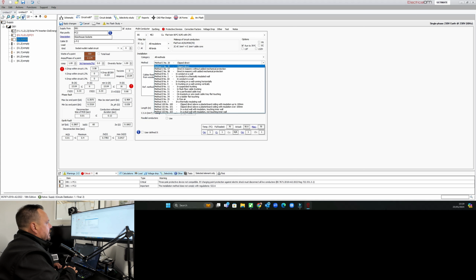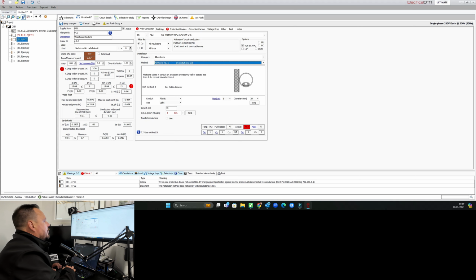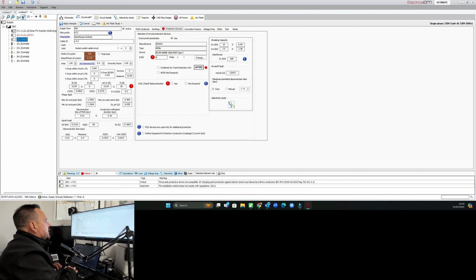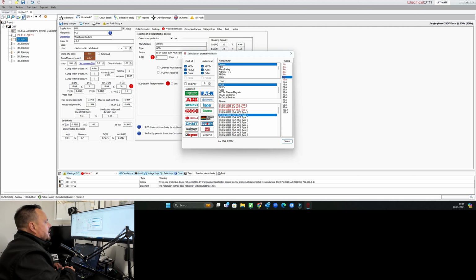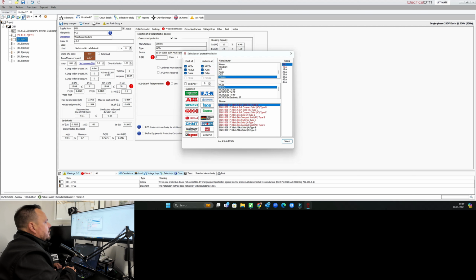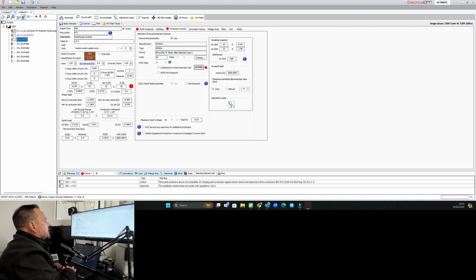This is going to be in conduit on a wall. So we'll pop that in there as well. Now, usually you'd use singles, but this is just really for neatness than anything, and also to use the LSF. And we'll do that in 4mm. Go to our protective devices now, and we can change the protective device. And again, we're on with our Proteus. Again, we're going for our RCBOs, and we've got our 10 kA we need here. We're going to go for a type C, and we'll set that to 32 amps.